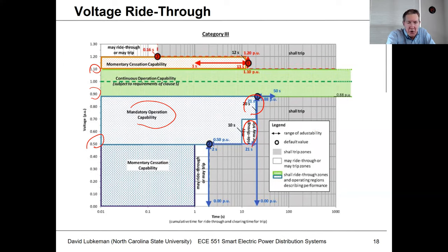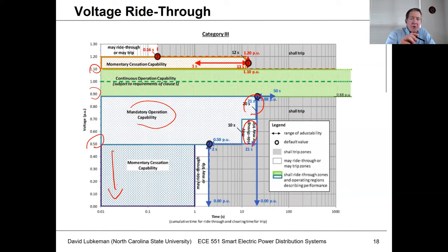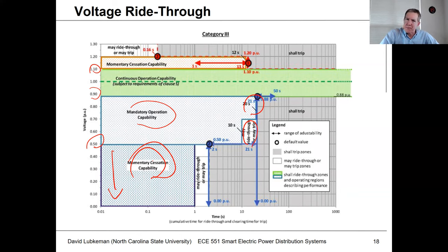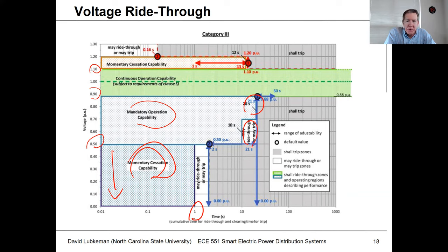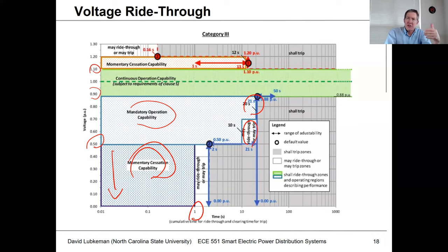When voltage drops below 0.5 all the way down to 0, that is, for all practical purposes, a disconnection from the grid. There's what they refer to as a momentary cessation capability. What this means is that the inverter is not injecting power into the grid, but it's kind of in a standby mode — floating online — so as soon as we connect back up again, it's ready to go. It doesn't have to go through a restart. Since this is a log scale, you can see it's got to be able to stay operational for up to a second. Usually by that time, most faults would have been cleared.